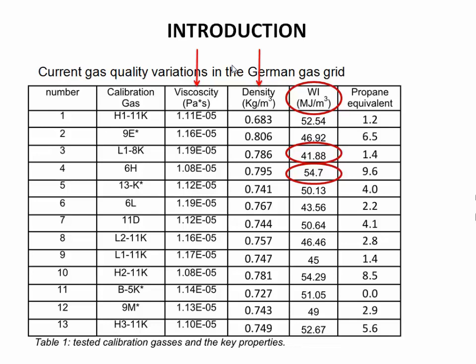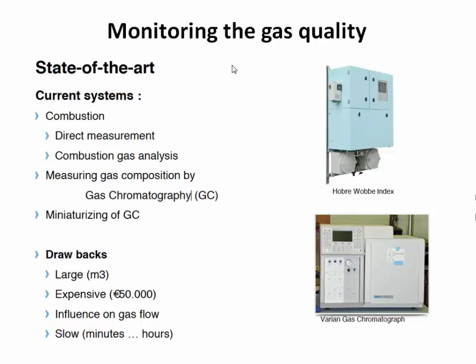Of course, there is already equipment for that, like the normal Wobbe index meter. But this is a very big device. It's 2 meters high and 1 meter wide and half a meter thick. And also the gas chromatograph. All of these systems are nice, and they will give you a very accurate, at ppm level, value of the Wobbe index. However, it's bulky equipment. It's expensive, it can go up to 70,000 euros. It has a large gas consumption, and the gas chromatograph is slow, typically of the order of minutes, maybe of hours. A real Wobbe index meter is fast.